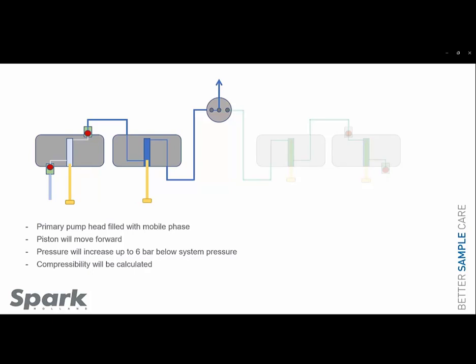During this increasing pressure, it will calculate its compressibility value. This is based on the distance which it takes to get to 6 bar below system pressure. There's the distance and the time. The inlet and the outlet check valve are closed.